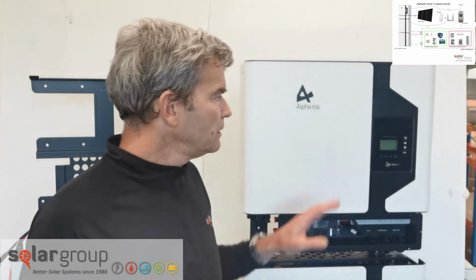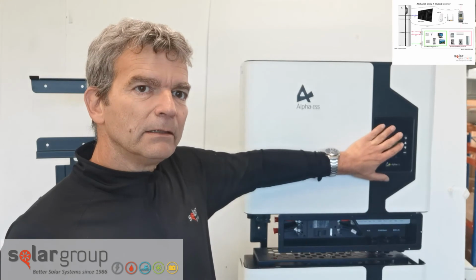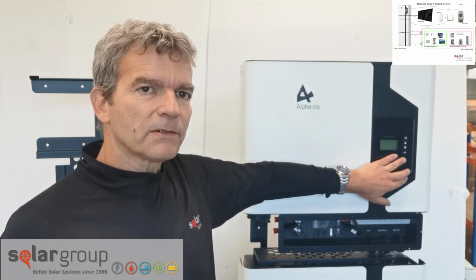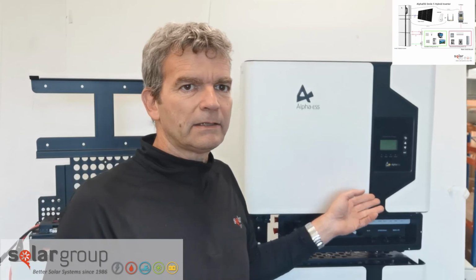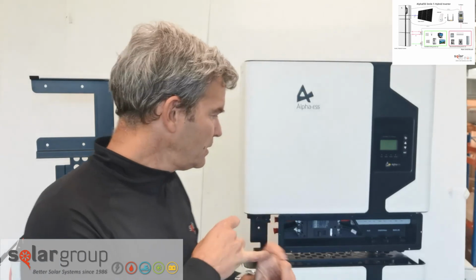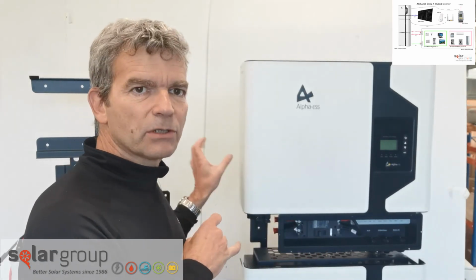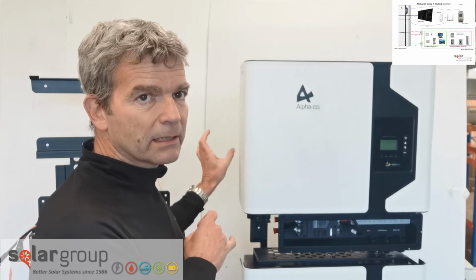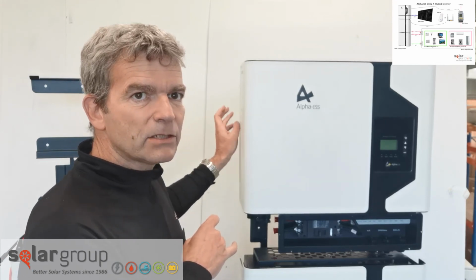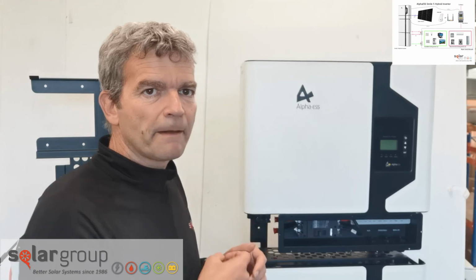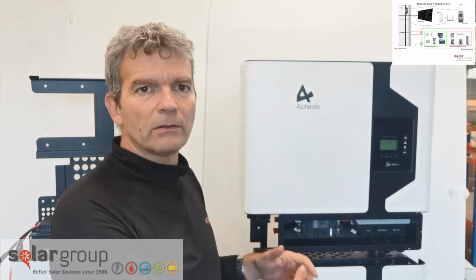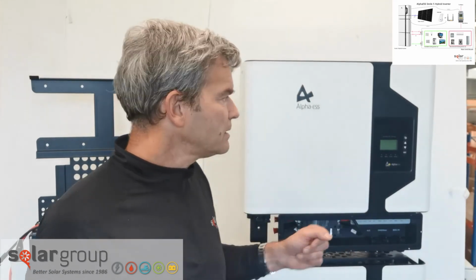Commissioning the unit, last but not least. Commissioning can be done without internet through this LCD pad, following the instructions. Like any other system, you turn on the DC from the solar panels first, using an external DC switch, and an external AC switch if you're far from the main switchboard. Then you turn on the AC, then the battery. The system should turn on with a 60 second delay.